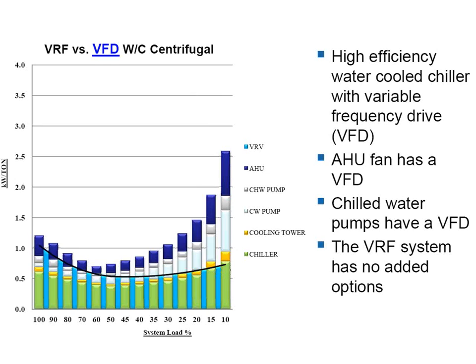Let's see what Tyler's question was. Does the water-cooled chiller versus the VRF system account for water or air-side economizer? And no, it did not account for that in this particular case. Probably for the same reason, the chart was made by a VRF guy. However, a lot of spaces can take advantage of a water-side economizer. Excuse me, I'm sorry, Tyler. It does take into account an air-side economizer. It did not take into account water-side economizing, if that makes sense. Because this particular example was based on VAV air handlers. So it did include air-side economizer in the energy model. It did not include a water-side economizer, which is what you would have done if you had a fan coil type job. Bill asked the same thing about the ventilation costs with the VRF, so we already answered that.